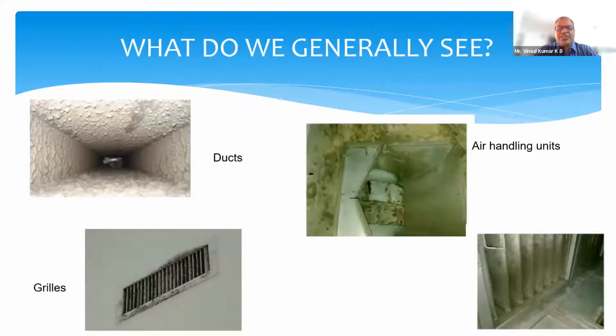Now, this is what we generally see across many places. You can see the duct coming out of the AHU, which is fully dirty. You can see the inside of the AHU, which is corroded, with a lot of fungus. The filters also have a lot of fungus, and the grill or the outlet is also corroded or has fungus in it. All this is because we do not have a proper maintenance team, or we don't have the facility to maintain. Sometimes we put AHUs in places where you can't maintain them. You cannot have a door that cannot be opened. So you can see this is the kind of system that we generally come across, and we should avoid that.